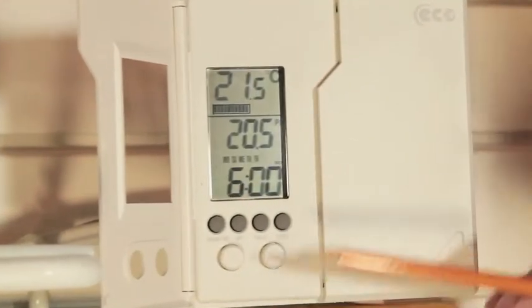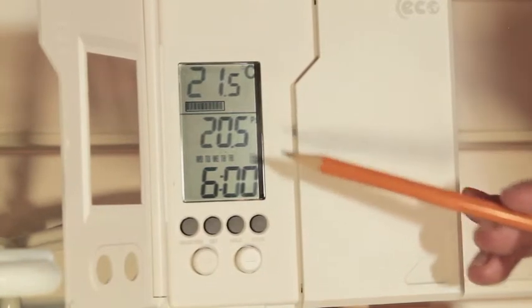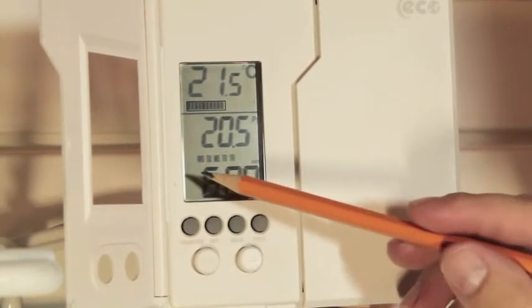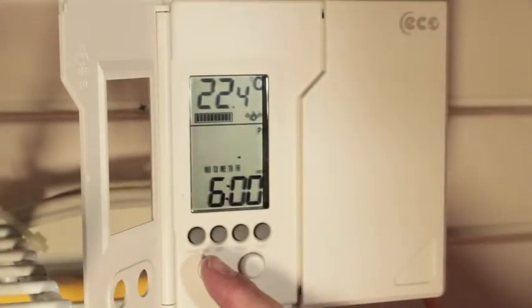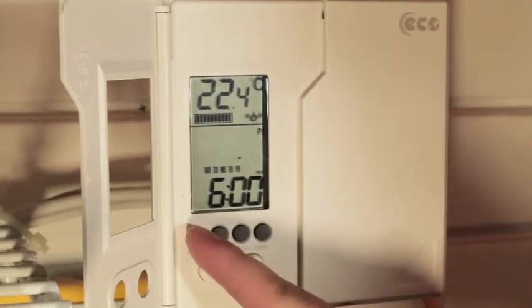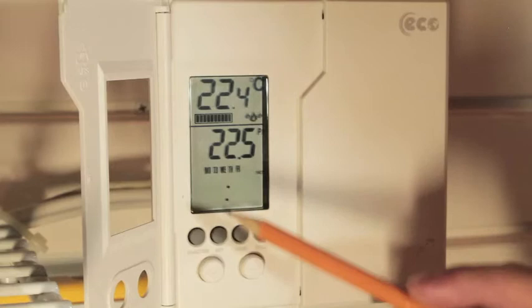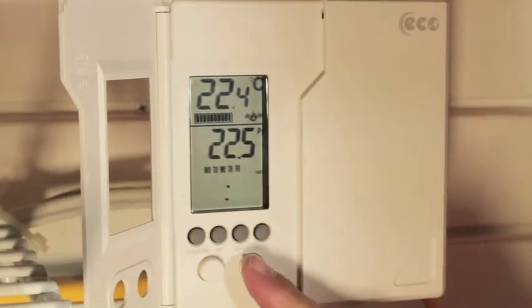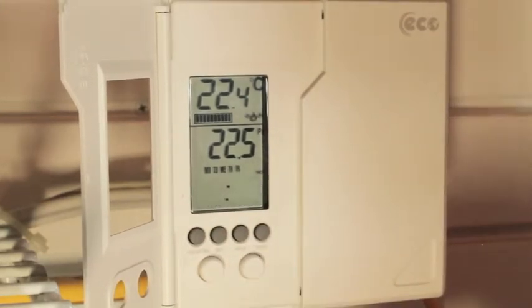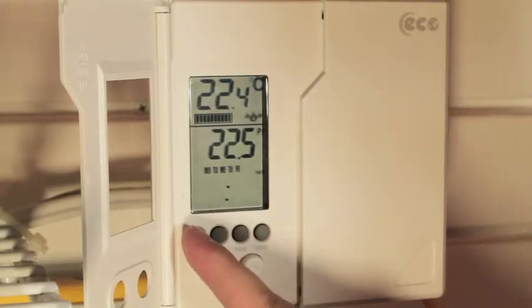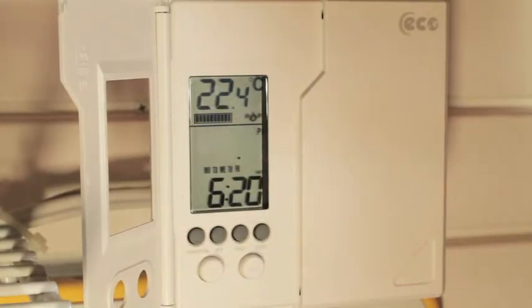To begin entering the program to the thermostat, press PROG once. The symbol for program one will appear on screen as well as all the letters for the days of the week. To adjust the temperature of program one, you can now press the arrow buttons. To switch to adjusting the time, press the usage time button. The time will now flash. This can now be adjusted by pressing the arrow buttons. To switch between the temperature and time, press the usage button.